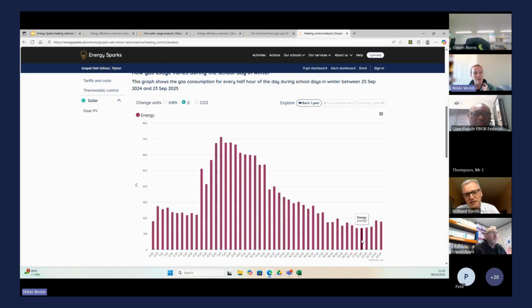Even if you're really risk averse and can't go down to the settings Richard mentioned, switching your heating off for 3 hours before midnight won't affect bacteria build-up in the pipes. Between midnight and 7 or 8am you're still circulating heat, but you can work this out from your chart. This school is using about £150 to £180 for every half hour, so for every hour they switch the heating off over the year, that's a saving of about £300.